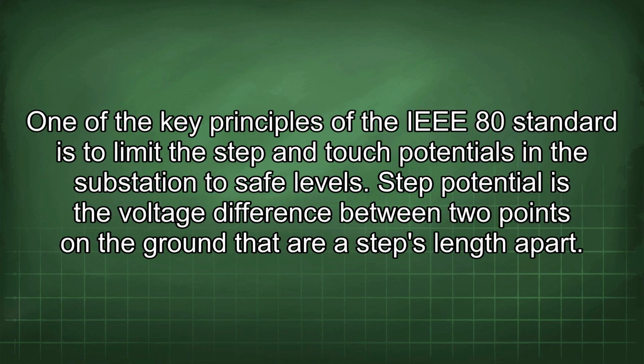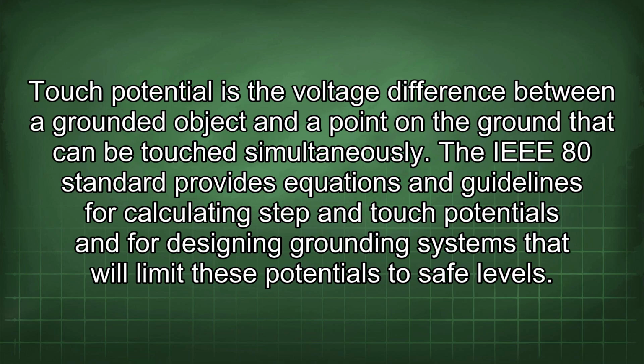One of the key principles of the IEEE standard is to limit the step and touch potentials in a substation to safe levels. Step potential is the voltage difference between 2 points on the ground that are a step's length apart. Touch potential is the voltage difference between a grounded object and a point on the ground that can be touched simultaneously. The IEEE standard provides equations and guidelines for calculating step and touch potentials and for designing grounding systems that will limit these potentials to safe levels.